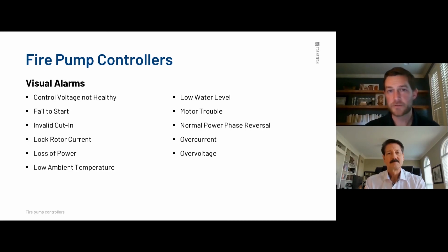And if it's a yellow alarm, like I mentioned, those are important alarms, but they're not critical alarms, and they pop up as yellow. For instance, pump on demand. The pump is running, and you'll see a yellow bar on the bottom of the ViZiTouch that says pump on demand. So any of the alarms that are happening are going to be flashing on the screen. If it's a yellow alarm, it's a yellow bar. If it's one of the critical alarms, it's going to be red. So if you have something major, like you've lost a phase, or the phases are unbalanced, it's going to pop up as red, and it'll be scrolling through that red section saying what the alarm is. In order to isolate that, you can go to the drop-down menu and tap on the alarm bell, and that will show you everything that's happening on the panel.